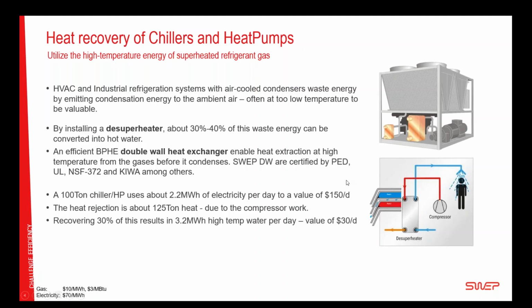If we take this example here, a 100-ton chiller, again, fairly big chiller, right? But it's an industrial application and it's still within the typical range here. A 100-ton chiller will use about 2.2 megawatt hour of electricity per day. It's $150 in our calculation. The total heat rejection from the condenser is about 125 tons due to the compressor work. So it gives 100-ton cooling, but rejects 125-ton heating.